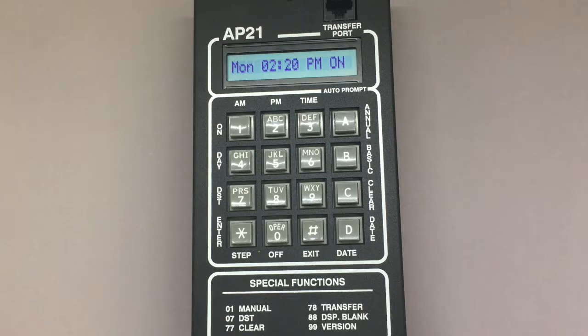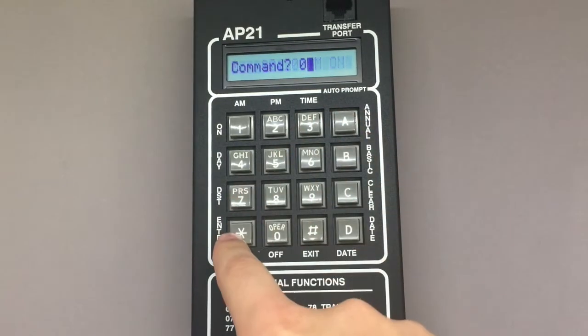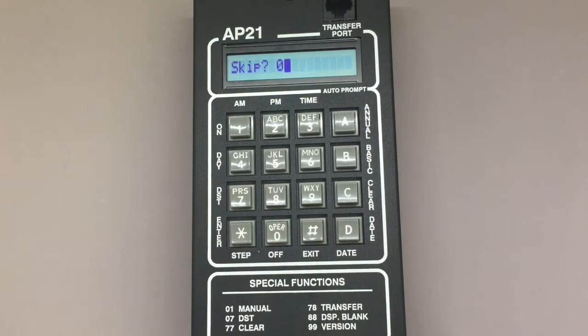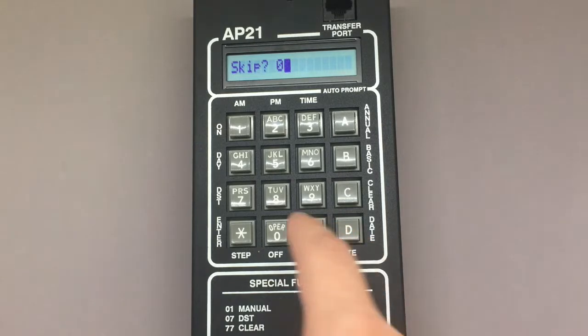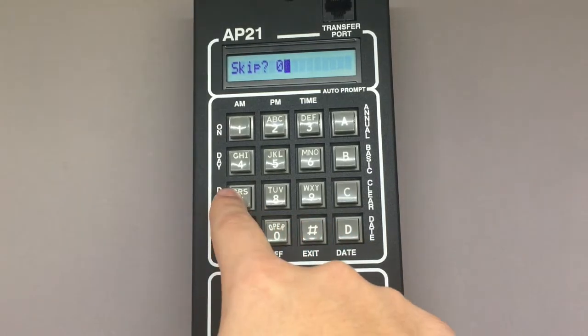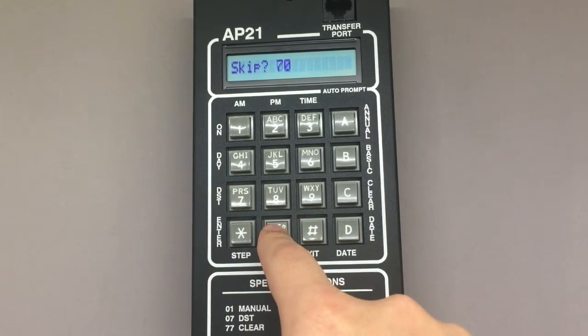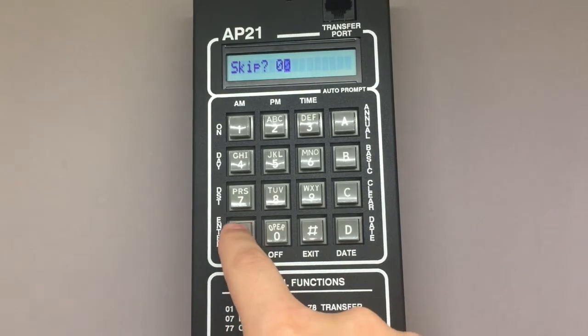To access the Annual Skip Plan screen, press A-star from the home screen. The AP21 allows you to schedule up to 10 skip plans, numbered 00 to 09. Since this is my first skip plan to program, I'm going to use 00. But if you want to view or edit a previously programmed skip plan, you can use the keypad to enter whichever number you wish. Pressing star sends you to the detail screen for the selected skip plan number.